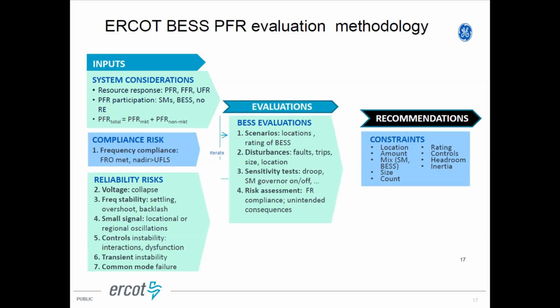Beyond frequency compliance in terms of those three metrics, we also looked at whether frequency recovery is fast enough. If you have oscillations, be it inter-area or local, are they damped enough? And if you have any overshoot or backlash -- there's this load response that kicks in at 59.7, a huge chunk of response -- what happens if you're just above or below that threshold, and how does that affect the frequency?